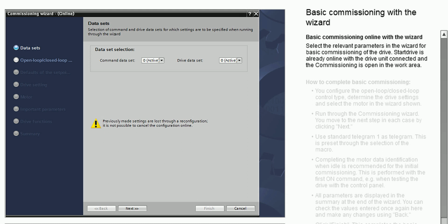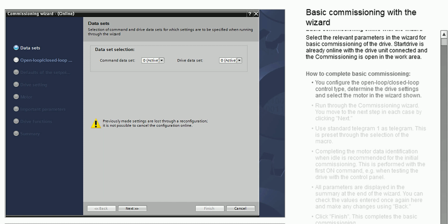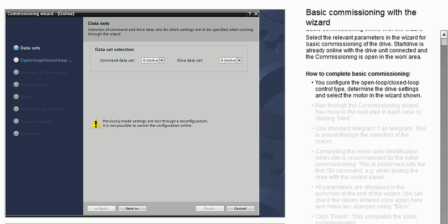Basic commissioning online with the wizard. Select the relevant parameters in the wizard for basic commissioning of the drive. Startdrive is already online with the drive unit connected and the commissioning is open in the work area. How to complete basic commissioning. You configure the open loop, closed loop control type, determine the drive settings, and select the motor in the wizard shown. Run through the commissioning wizard. You move to the next step in each case by clicking Next.